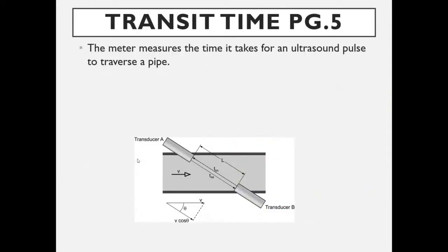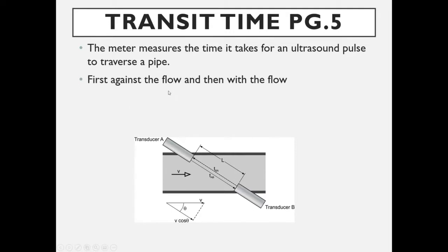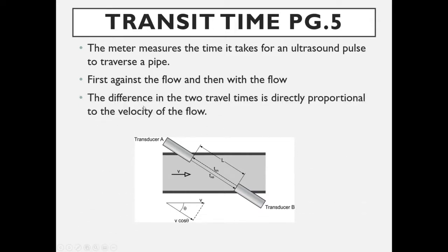Transit time is the second technology. This meter measures the time it takes for an ultrasonic pulse to traverse the pipe — it crosses the full pipe diameter rather than reflecting off particles. The signal travels against the flow and then with the flow. The difference in the two travel times is directly proportional to the velocity of the flow.